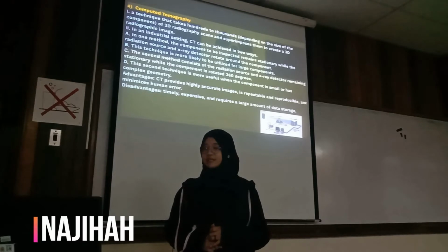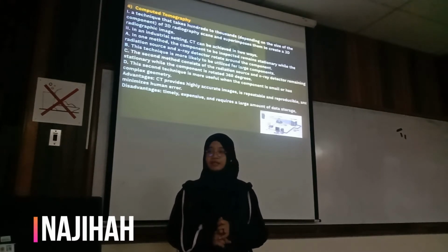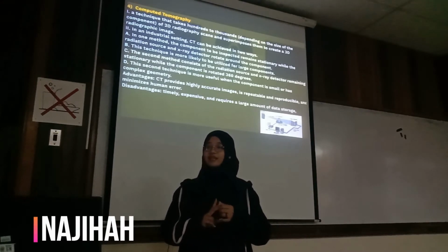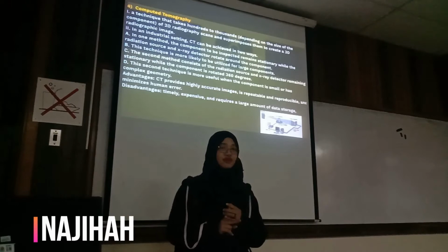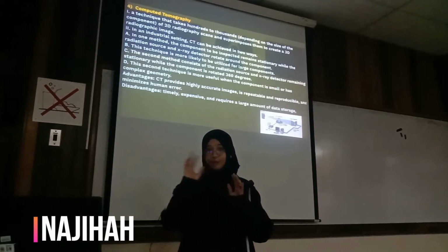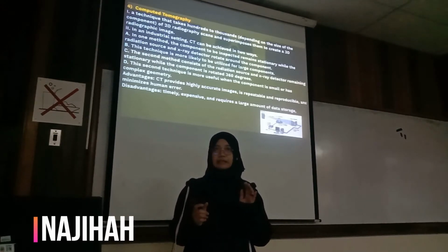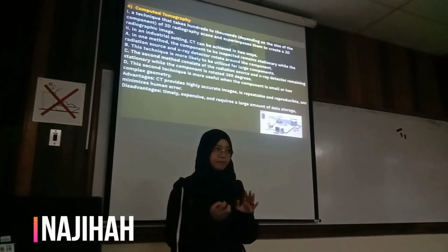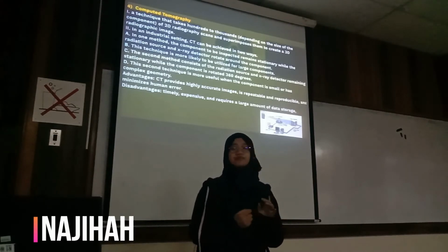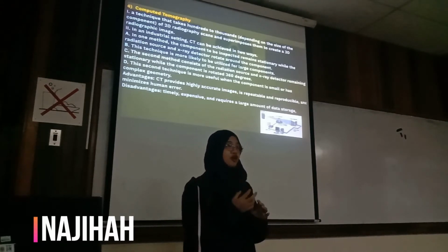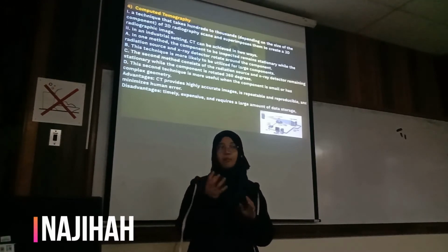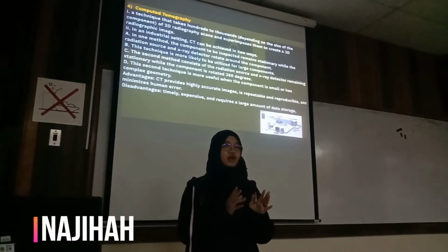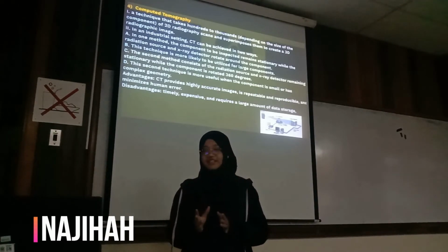The first method is that the component remains stationary, but the X-ray radiation sources and X-ray detectors rotate. This method is usually used for bigger components. The second method is usually used for small components, where the small component rotates 360 degrees and the X-ray detector and radiation sources remain stationary.